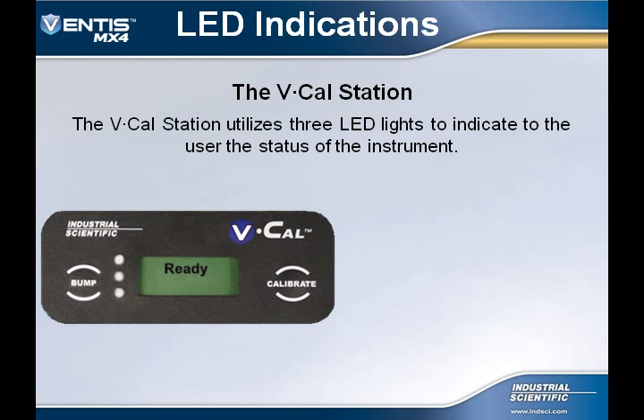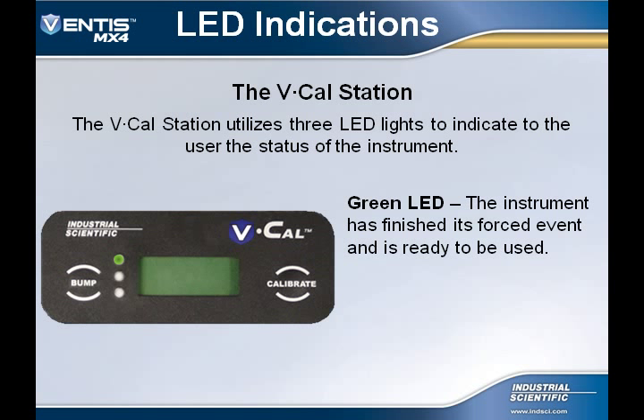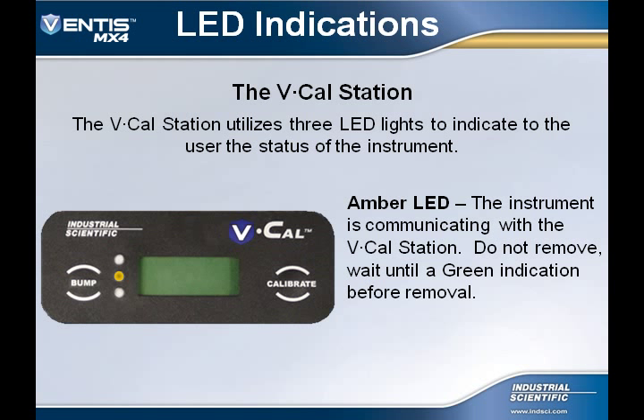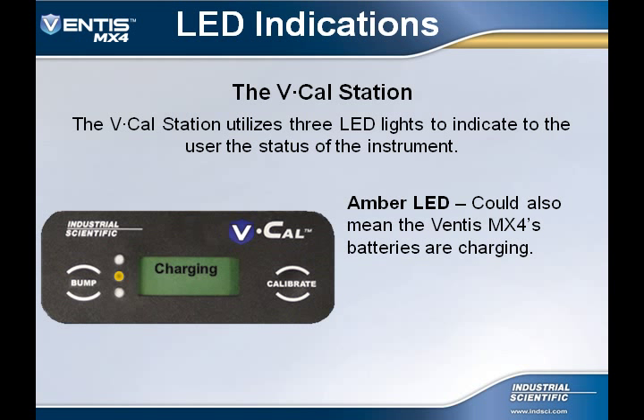The VCal utilizes three LEDs to indicate the instrument status. The green LED indicates that the instrument has finished its forced events and is ready to use. The amber LED indicates that the instrument is communicating with the VCal station. Do not remove until a green LED indication. The amber LED could also indicate that the Ventis MX4's batteries are charging.